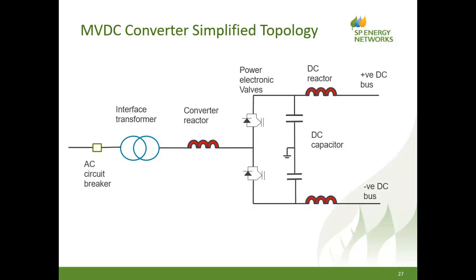We have a converter reactor, or we may have a converter reactor. Not all designs need this. We will have a DC reactor. You've seen this in the layout that Kevin showed. There are DC reactors, one positive, one negative. So this represents the simplified topology of the MVDC circuit. And indeed, this is very similar to HVDC circuits, which are very much the same technology, but the details of equipment are quite different. For the power electronic valves, I've shown a single symbol for an IGBT, but of course there are many, many IGBTs in series to hold off the 27 kV DC voltage, not simply one switching device, but for the purposes of PowerPoint, I've just shown one.